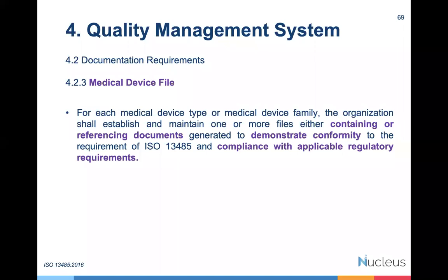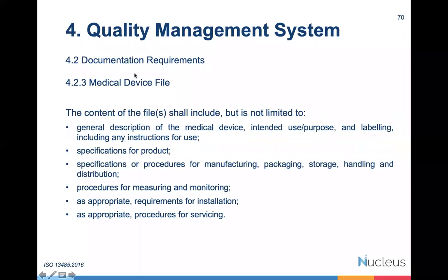So what should be the content of the medical device file? They give you some minimum requirements. Based on your role, this is applicable. If a company is not doing any installation, this may not be applicable. If you're not doing service, leave it. But look at this first four. This is a shall requirement. You must address this.